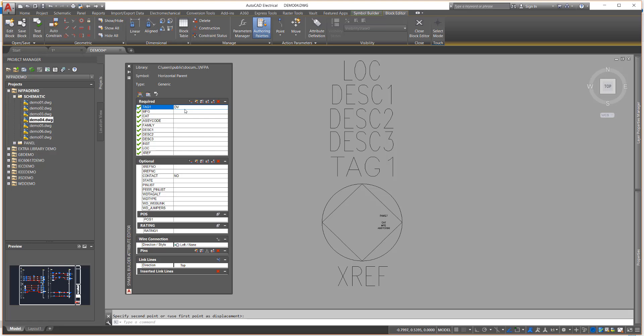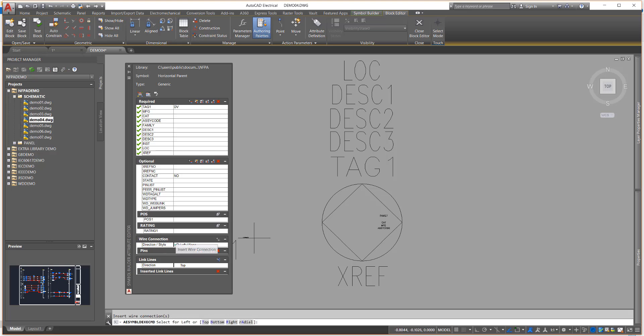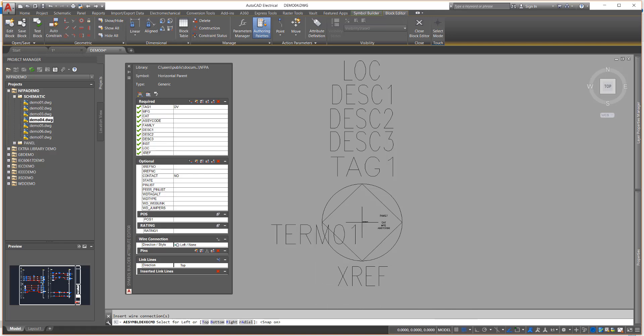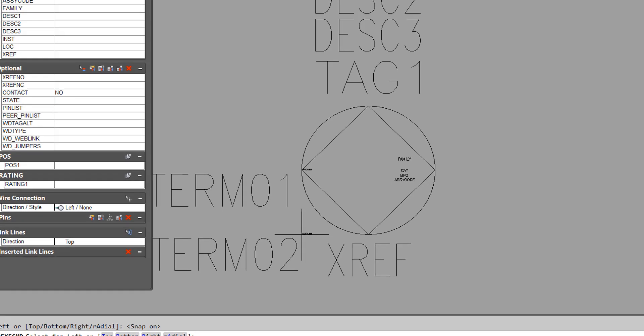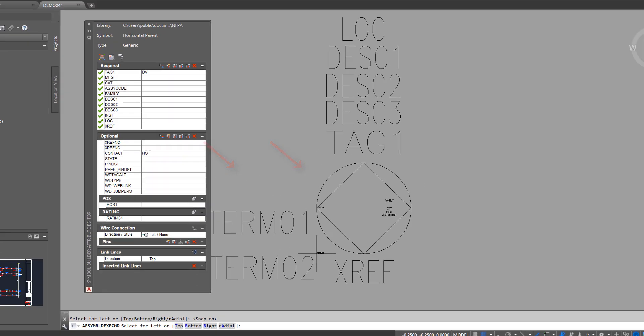Next you will add the wire connection points. Select the left none option and choose the insertion point or wire connection point on the symbol. Be sure to use some kind of object snap to position the attributes exactly. Two attributes are inserted at the same time: the wire connection attribute TERM01 and TERM02.